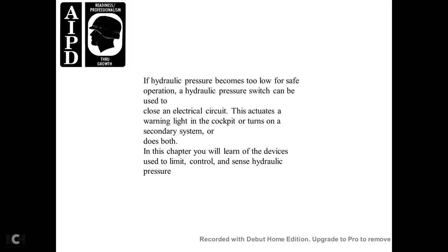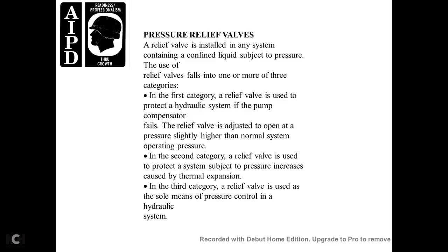Pressure Relief Valve. A relief valve is installed in any system containing confined liquid subject to pressure. The use of relief valves falls into three categories: first, to protect the hydraulic system if the pump or compensator fails — the relief valve is adjusted to open at pressure slightly higher than normal system operating pressure; second, to protect the system subject to pressure increases caused by thermal expansion; and third, to serve as the sole means of pressure control in a hydraulic system.